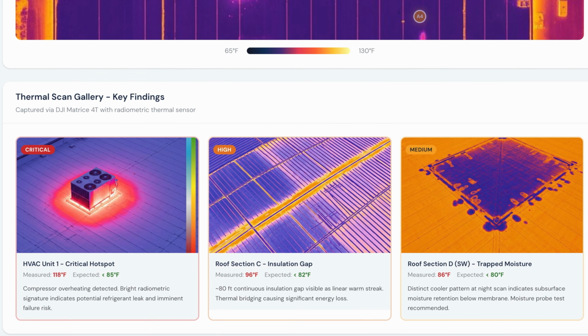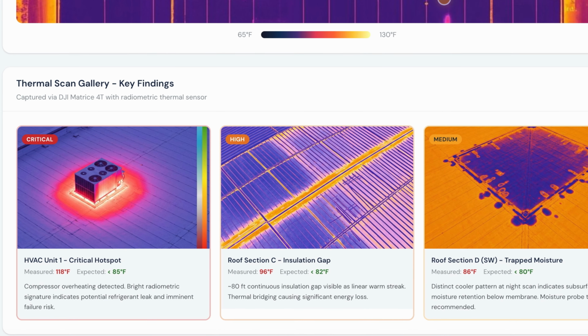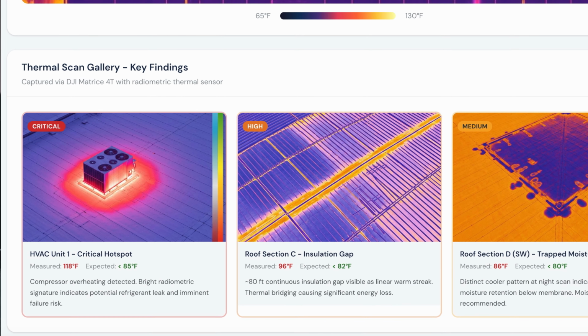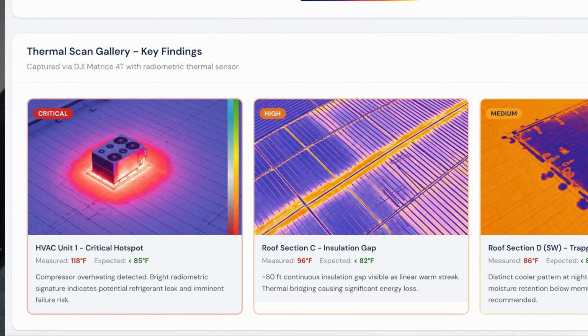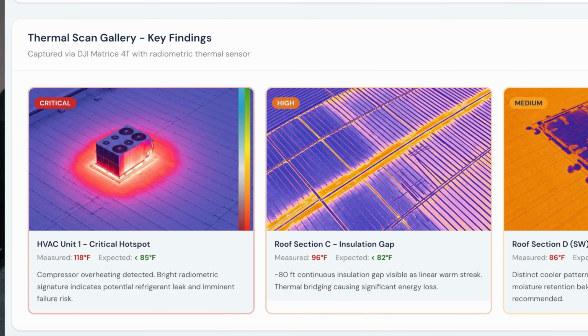The scan flagged 10 anomalies total. 4 of those needed immediate or near-term action. 2 were critical. Let me walk you through all 4. HVAC Unit 1 came back at 118 degrees. Expected operating range is 85 or below. That is a 33-degree delta, and it tells you the compressor is overheating.